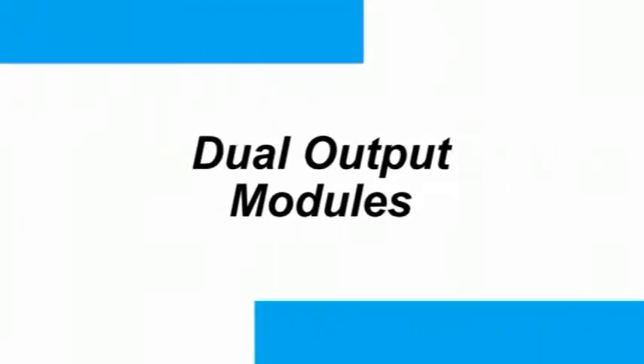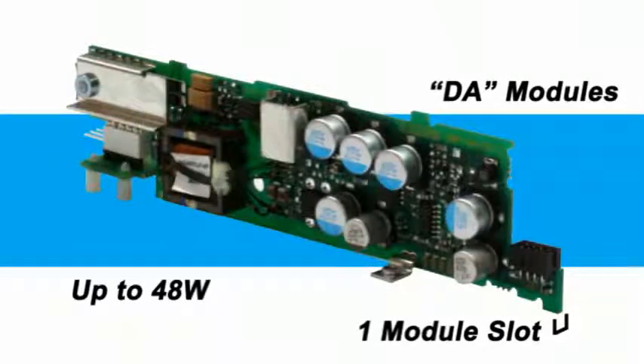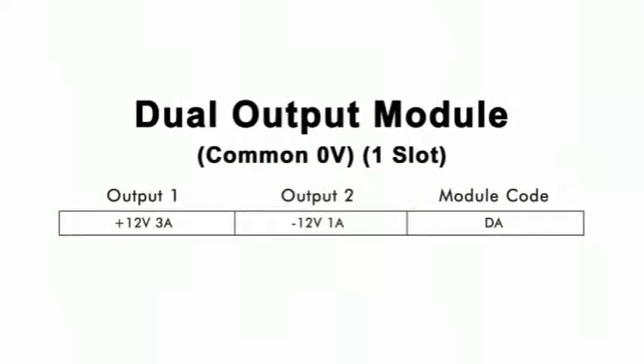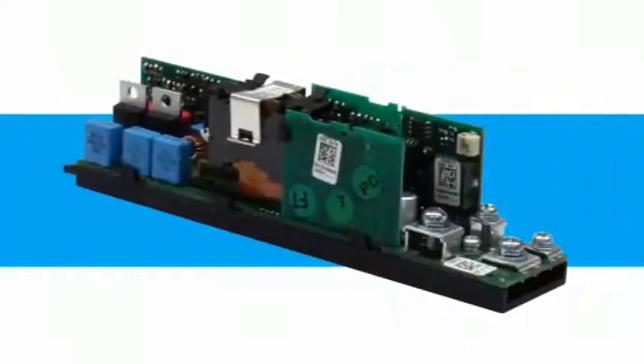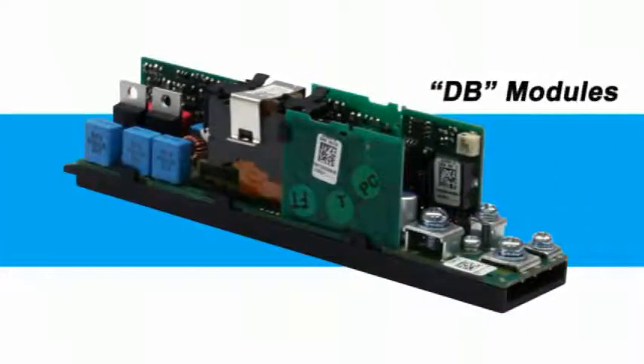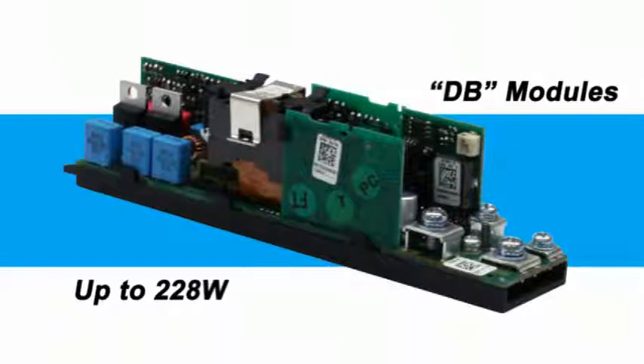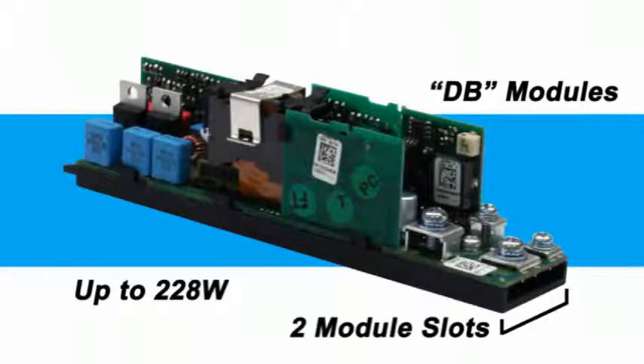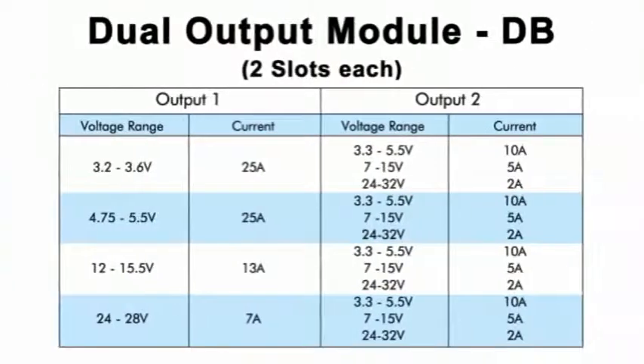The DA dual output module takes up only 1 slot and provides plus and minus 12 volt outputs at up to 48 watts total. Higher power dual output modules are available with various volts and amps ratings at up to 228 watts to meet the customer's needs. For special output voltages, these modules have adjustable outputs. Each of these modules requires 2 module slots of space.